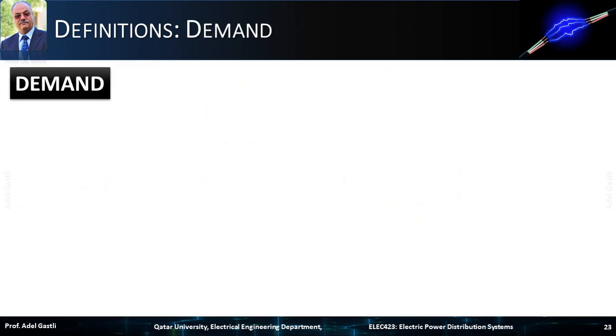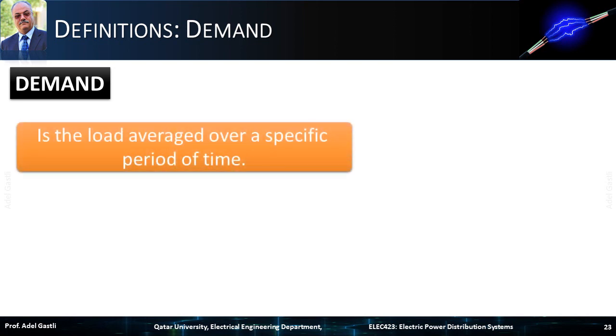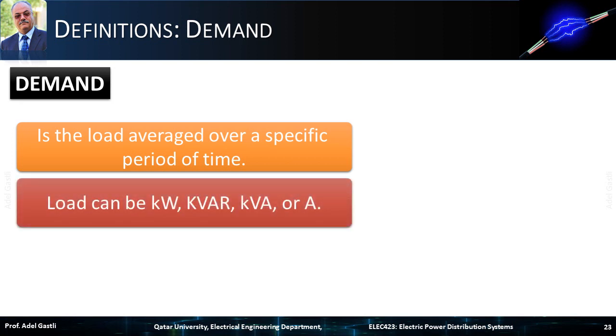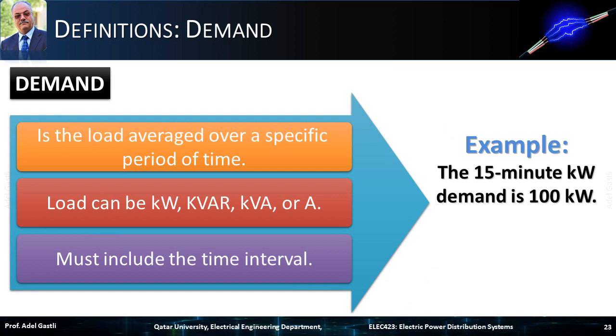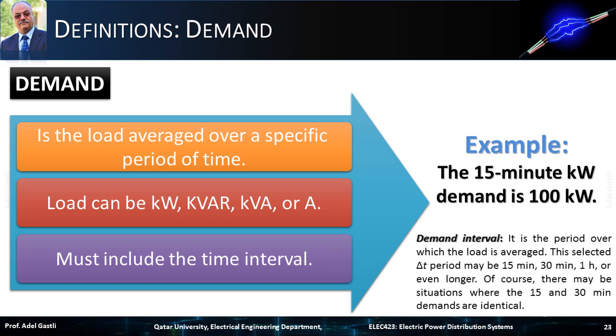Now let's look at definitions of some important parameters useful for the analysis of the distribution system. We start with demand: it is defined as the load averaged over a specific period of time, where the load can be expressed in kilowatts, kilovolt-ampere reactive, kilovolt-ampere, or amperes. Demand must also include the corresponding time interval during which the load is averaged. For example, the 15-minute kilowatt demand is 100 kilowatts. The demand interval is the period over which the load is averaged — this selected period may be 15 minutes, 30 minutes, 1 hour, or even longer.